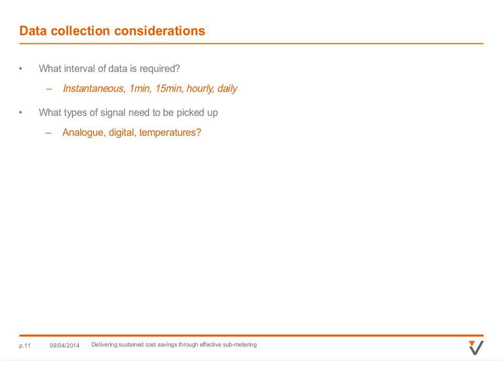What kind of things do you need to pick up? Analog would be something like a flow rate typically, it might be a temperature, or maybe a pressure. Or maybe you just want digital, so that would be like a pulse - something telling you how many things have happened. Typically electricity meters would give a pulse every time there's a kilowatt hour, for instance. So that has an impact on what kind of data collection you need.